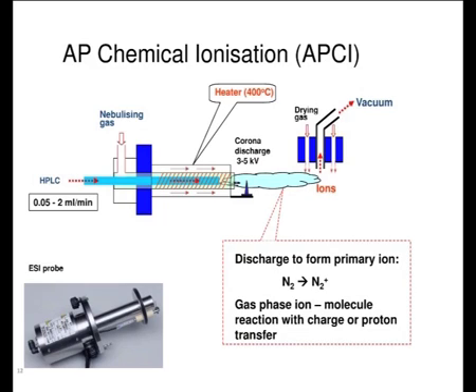The next technique is APCI, the atmospheric pressure chemical ionization technique. ESI is used for polar compounds, APCI is used for mid-polar compounds. How does it work? Here also there are two concentric capillaries, and there are heater plates. Here also we are using a nebulizing gas. It nebulizes between this heater plate that is maintained at a high temperature, and it forms small droplets. The compounds are not yet ionized. There is a corona discharge needle that is maintained at 3 to 5 kilovolts.